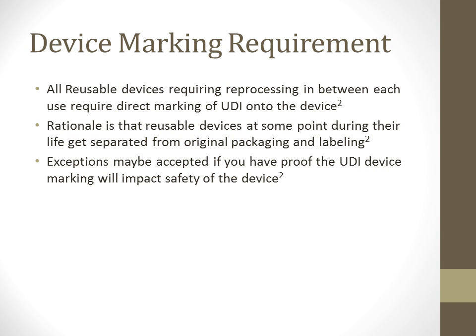There are some exceptions that may be accepted. That's part of the rule: there are some exceptions if you can prove that UDI device marking will impact the safety of the device with the patient. And there's also some exceptions if it's too small. Sometimes it's really tiny and you're not able to put the UDI in a good readable format.